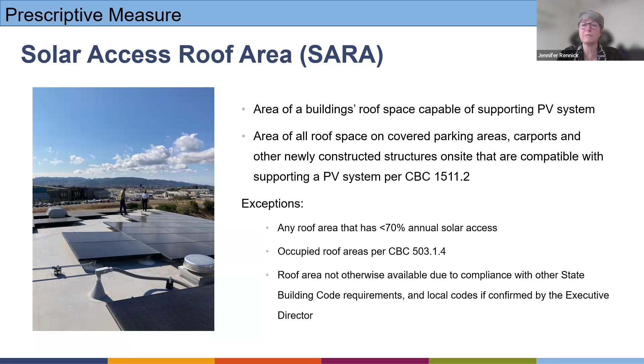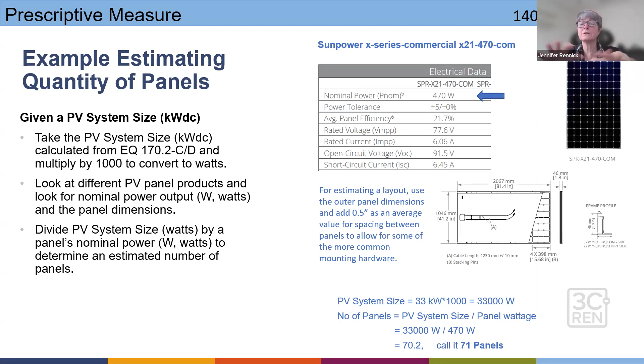I put this in here as an example of how to estimate the quantity of panels, because a lot of times folks say, okay, I see how I can calculate what that PV system size is, kilowatts DC, but now what? And just as an example, you could use this panel as an estimate because it has dimensions, and use a rule of thumb for allowing a little space between the panels. And you can take that size requirement for the system and divide it by 470 watts and get an estimate of the panel quantity. And then you could start to see how you might lay it out for your project.